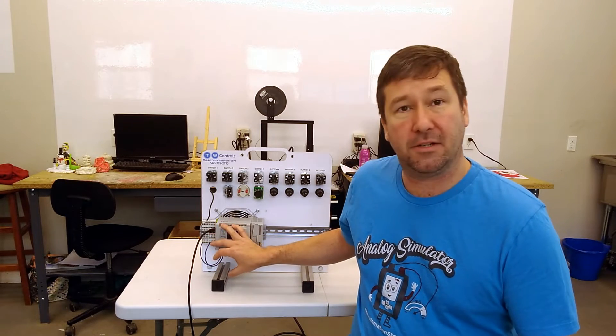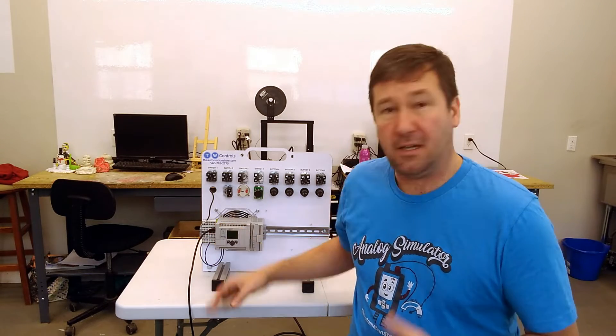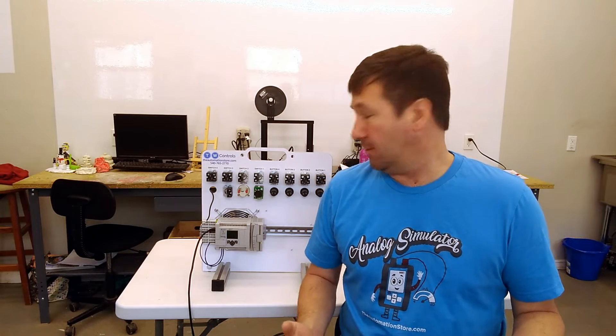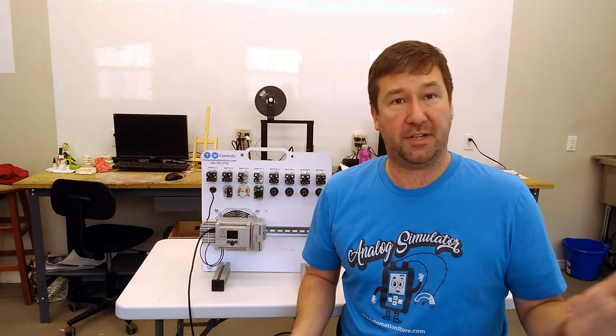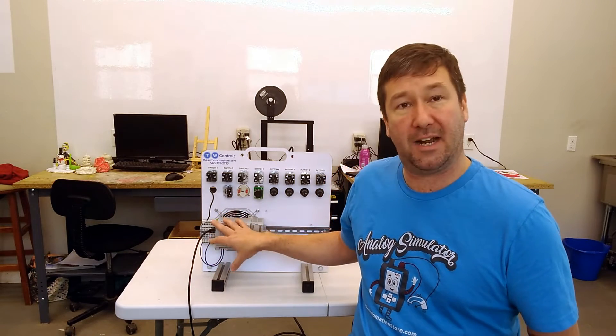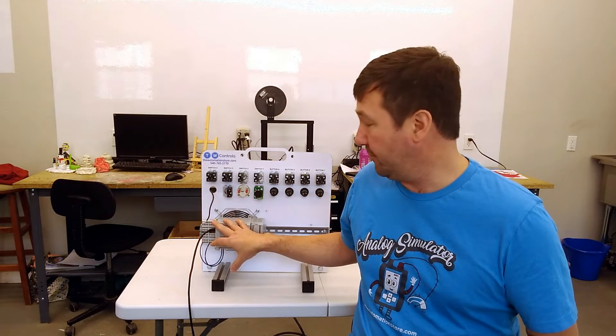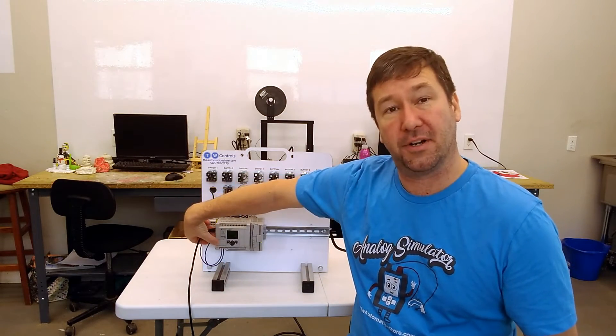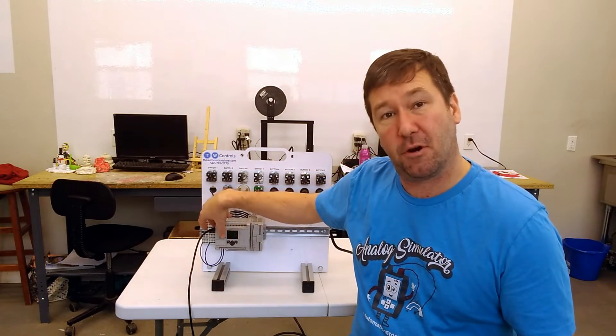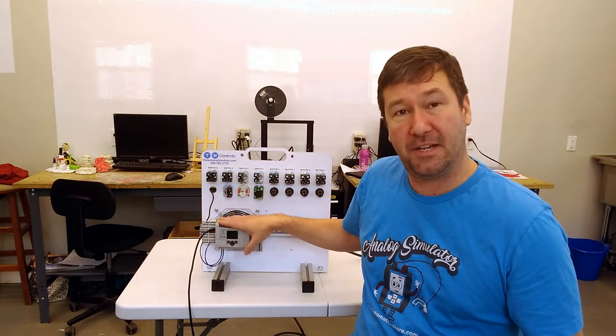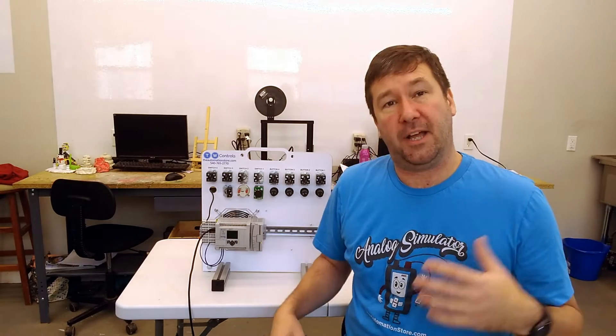You're going to have to use either a BOOTP device such as our IP Explorer, or you could use Allen Bradley's BOOTP software and assign an IP address to it, or you can go to the serial port and download your program with the IP configured.